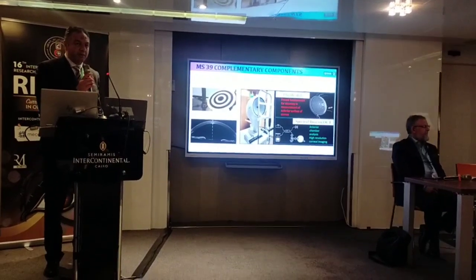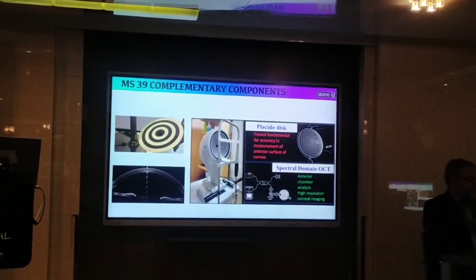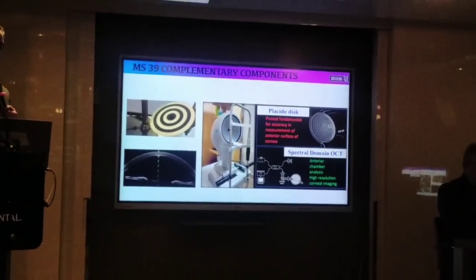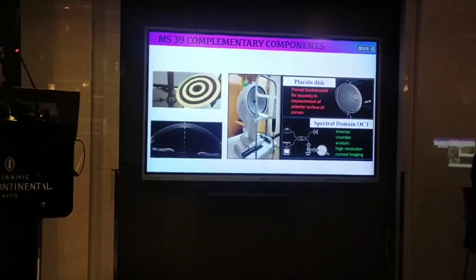The MS39 combines OCT-based tomography — which is a spectral domain OCT — with a Placido disc, offering sensitive and accurate topography plus a more accurate tomography compared to the Scheimpflug camera, which is affected by dry spots and faint corneal opacities. The OCT-based tomography is not affected at all by dry spots or corneal opacities.